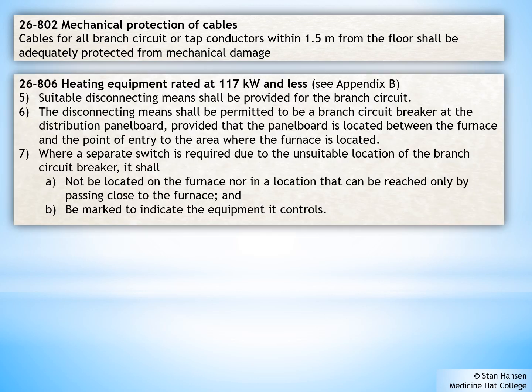I also need to go back to Rule 26806 and look at subrules 5, 6, and 7. These talk about the disconnecting means I would have for my typical furnace. Each furnace needs to have a disconnect. Subrule 6 tells me that can be a breaker if the breaker is between the entry point and the furnace. If the breaker is after the furnace, you need to have a separate disconnect switch. Keep in mind, it cannot be mounted to the furnace or the ductwork or anywhere where you need to pass the furnace to reach it, and it must be labeled to indicate what it controls. The reason for this is if your furnace is burning up, in order to kill your furnace, you don't want to have to go through the fire to get there. So make sure the separate switch is located somewhere where it's intelligent and it's easily accessible.